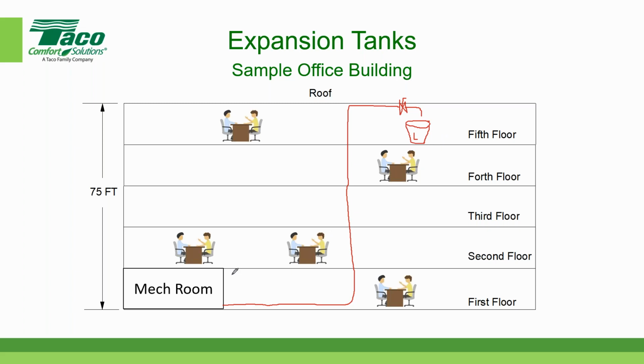So let's say I put another valve down here, and I'm going to open this valve and fill my piping system with water. Fill it up until it gets all the way to the top, and I just get a couple of drops of water coming out of my bucket. Then I close this valve. I just opened it to fill the piping system. And again, let's assume that the vertical pipe is 75 feet, from the highest point of the building to the lowest point in the building.